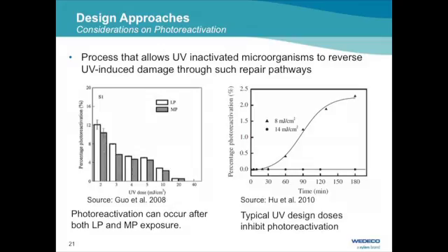And this dose formula is also used for the control of the system. Now, before concluding, I would also like to talk a little bit about photoreactivation. Yes, it happens, because this is a natural process of the organisms which are exposed to sunlight and which need to have some repair mechanisms. And it actually happens for both low pressure and medium pressure systems, as you see here.